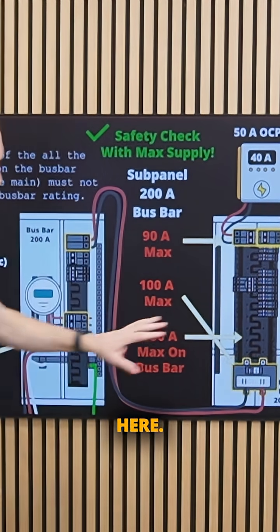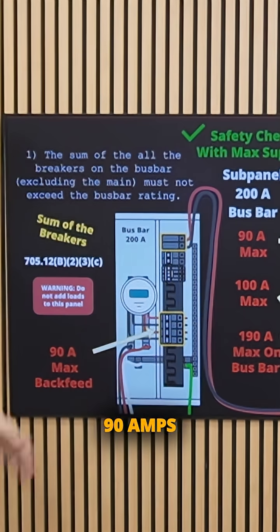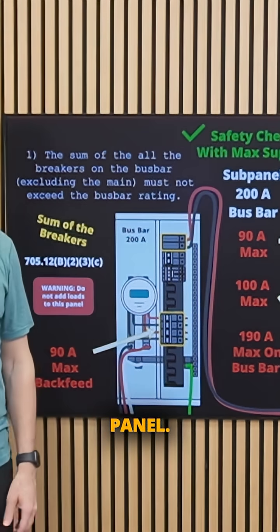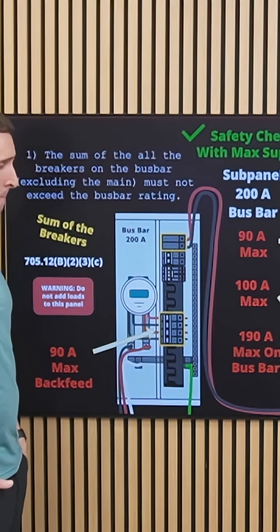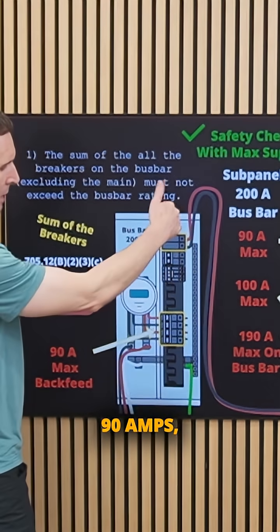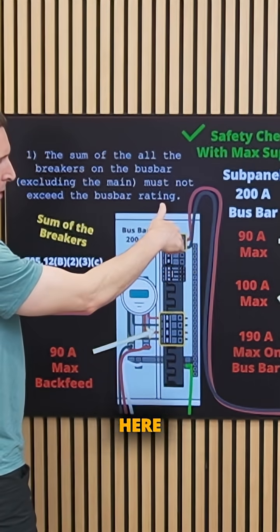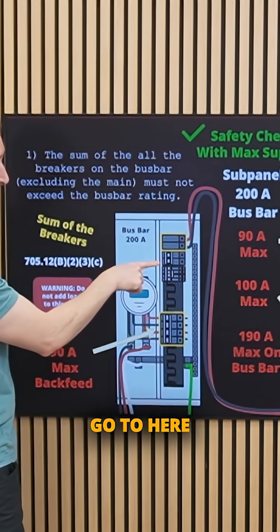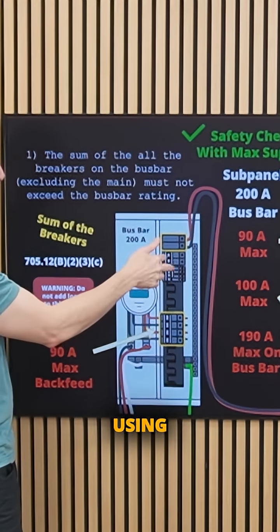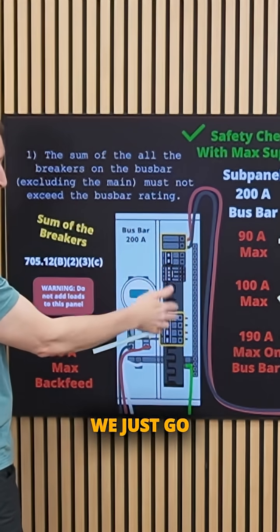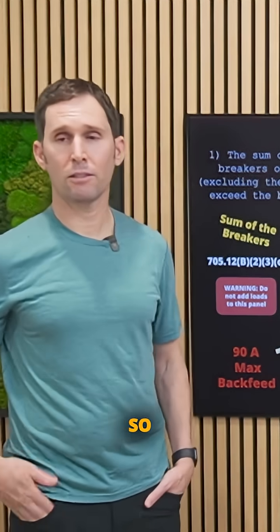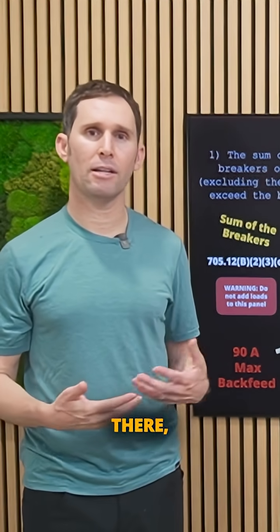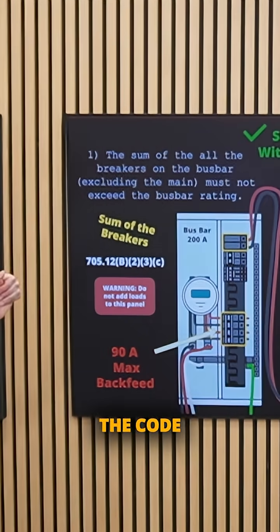Now let's look at this main panel. We're back-feeding 90 amps here because the total loads and supply never exceed 200 amps. Where does that 90 amps go? It lands on the bus bar. It can feed the loads on the panel, and if those loads aren't on, it flows through the bus bar, through the 200-amp main breaker, and back to the grid. There are no safety issues and no code issues — we're using the other piece of code: the sum of the breakers rule.